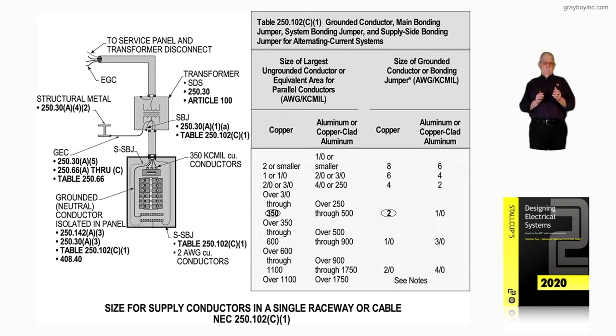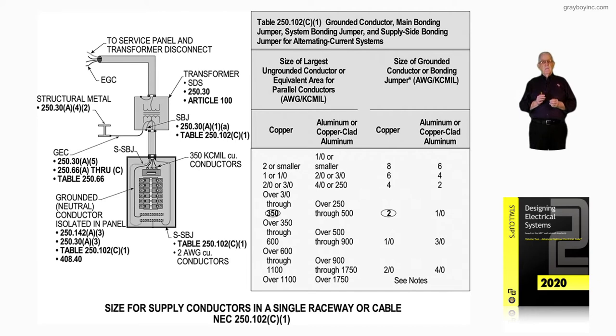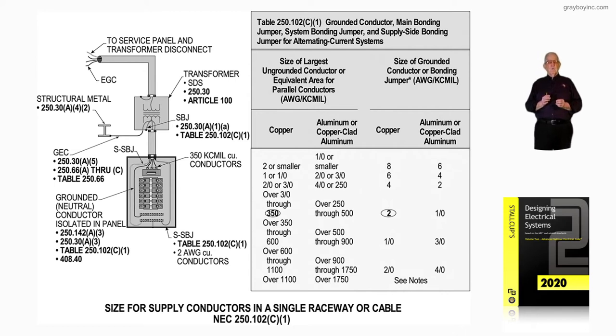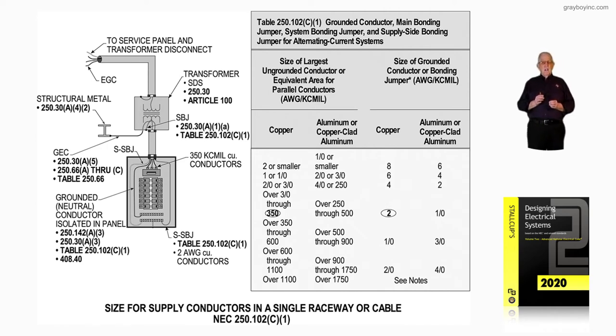To the left we have structural steel that meets the requirements of a grounding electrode in accordance with 250.30A4 item number 2. We also have listed the grounding electrode conductor per 250.30A5, using Table 250.66. If we're not using Table 250.66 to select the electrode, we would use 250.66A through C. Notice the grounded conductor itself is isolated in that panelboard in accordance with 408.40, as required by 250.142A and 250.30A.